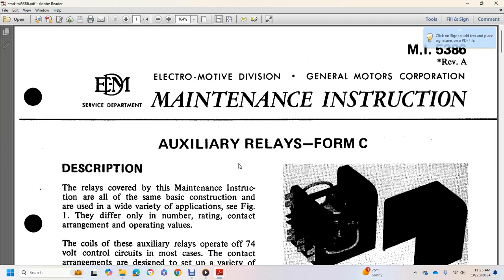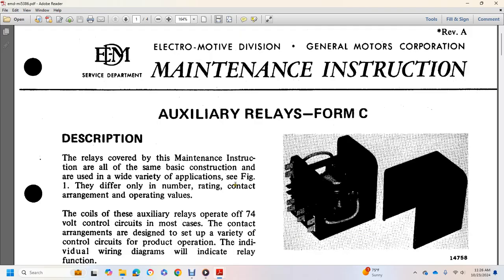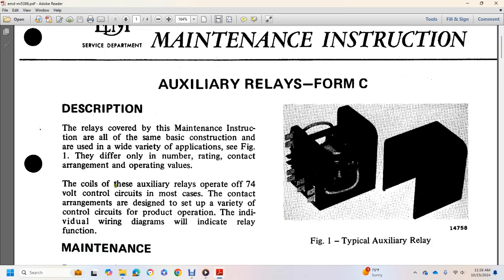Electro-Motive Division, General Motors Corporation. Maintenance Instruction, Auxiliary Relays Form C, Maintenance Instruction 5386, Revision A. Relays covered by this maintenance instruction are all the same in the basic construction and are used with a variety of applications. Figure 1 shows that they differ only in the numbered rating, the contact arrangement and the operating values. The auxiliary relays operate at a 74 volt control circuit, and in most cases the contact arrangement is designed to suit a variety of control circuits. Individual wiring diagrams will indicate the relay function.